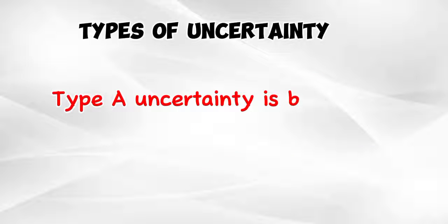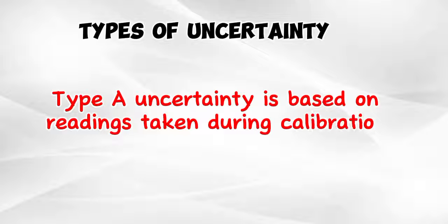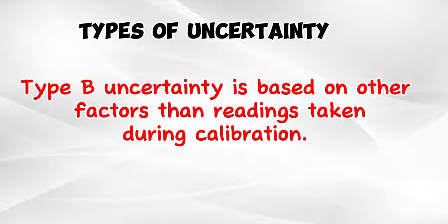Type A Uncertainty is based on readings taken during calibration. Type B Uncertainty is based on other factors than readings taken.